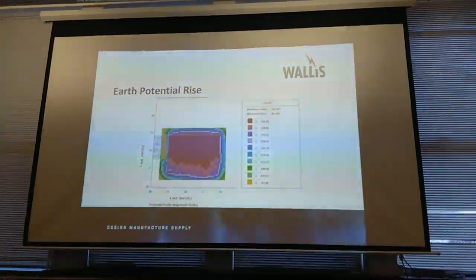Going back to that store site that we were looking at earlier, because we've got the rebar in the slab itself, that's all connected in, so that's potentialised the ground there, but it's actually pulled it down to 160 volts, and as you creep away from that, you can see between 160 volts there and creeping out to sort of 130 volts there. That's a brilliant site. The ground resistivity was brilliant there. The bulk supply point was only just up the road, so it was fantastic because I would say probably 80% of the fault current went up the cable sheath. So actually the general mass of earth saw very little fault current.